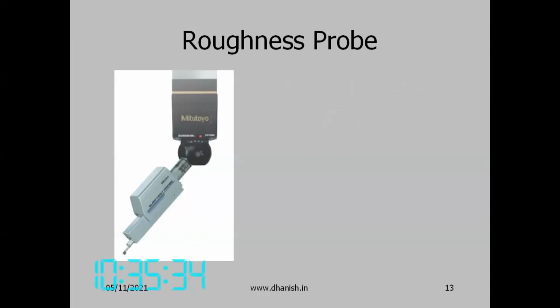Recently, the main purpose is to speed up the inspection, to do the inspection very fast. Many times, for surface finish measurement after dimension measurement, you have to take the workpiece elsewhere to measure the surface finish. So a company has come up with a solution, a roughness probe. The roughness probe is attached to the arm of the CMM and can be kept at any angle so that the stylus moves parallel to the workpiece surface, and we can measure surface finish. If you recall, the detector system can also be moved about, so we need an interface with the probing system.